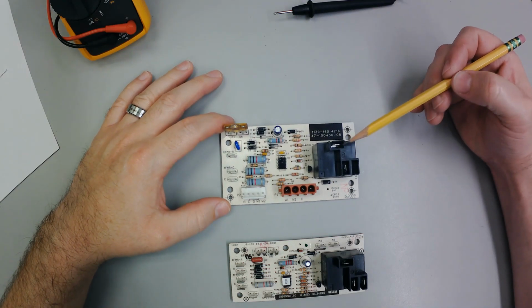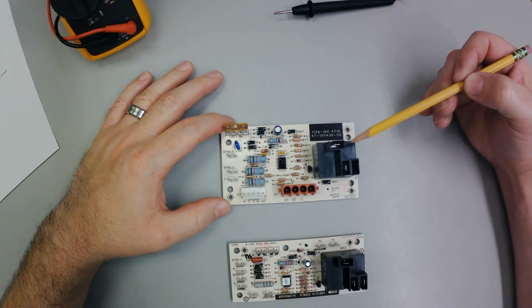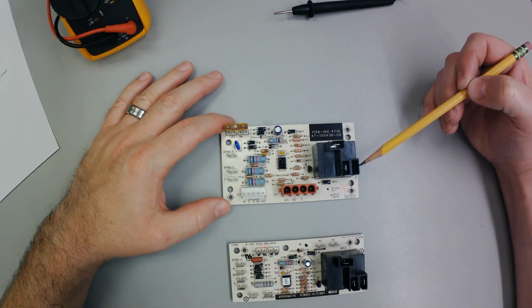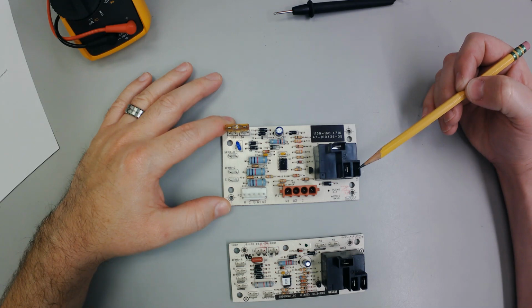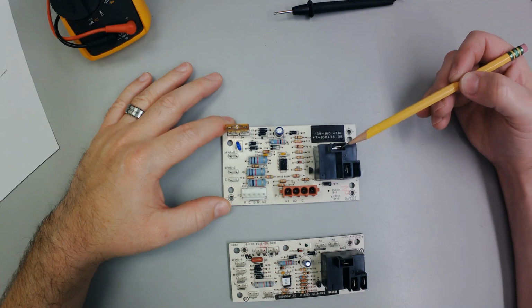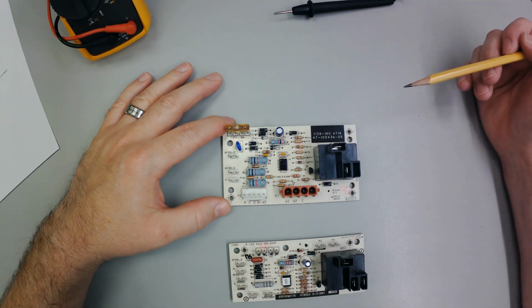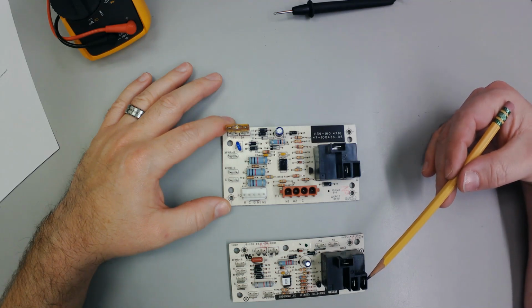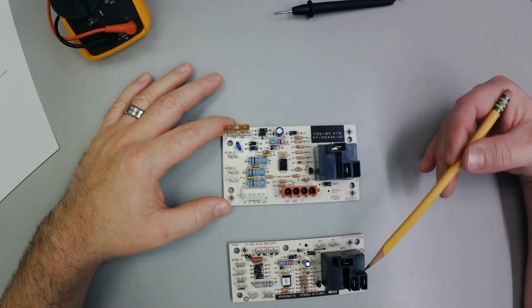But the reason, to me, that this fan relay doesn't have a normally closed switch is because it doesn't need one. If they needed one, they would have provided it. This relay has to close every time the fan needs to come on. There's no other way around it. The Goodman, I've got a normally closed circuit, which is like not even having a switch there.